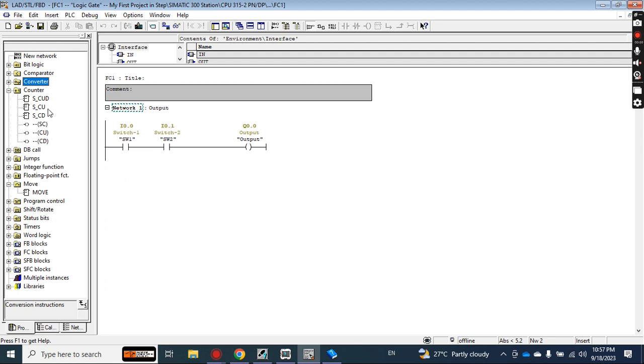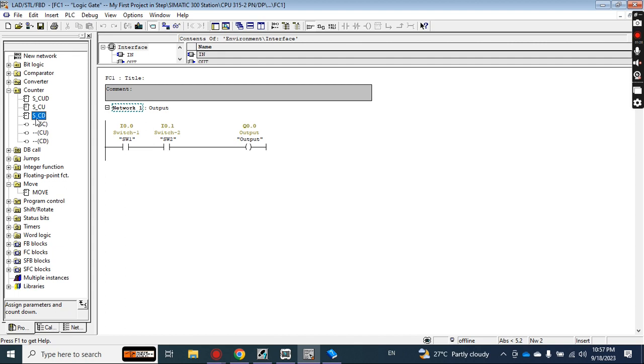There are three types of counters. Number one is CUD — Counter Up and Down — which can be used for both up count and down count at the same time. The second is Count Up, which only counts upward from zero. The third is Count Down — if you set a preset value of 10, it will count down from 10 to 9, 8, and so on.